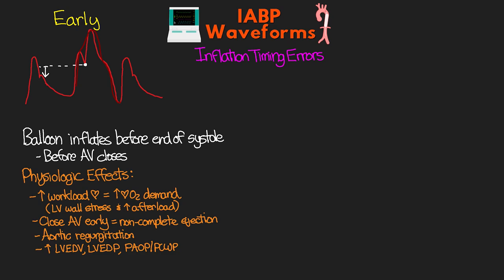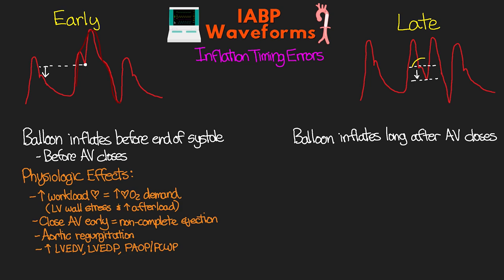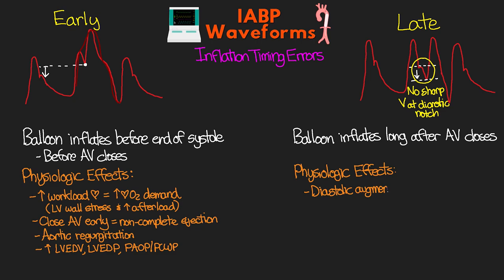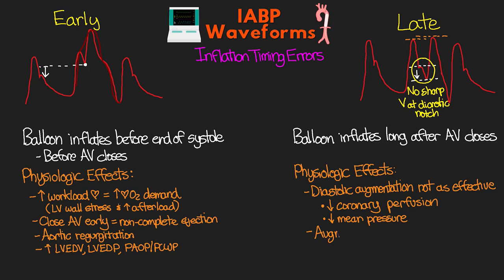The next timing error is late inflation. Here the balloon is inflating after the aortic valve has closed, leading to suboptimal diastolic augmentation. You won't see a sharp V at the dicrotic notch. The big physiologic effect is that diastolic augmentation is not as effective, meaning less coronary artery perfusion and a decreased mean pressure. You may also see the augmentation pressure equal to or even less than the systolic peak pressure, whereas normally we'd expect the augmented pressure to be much higher.